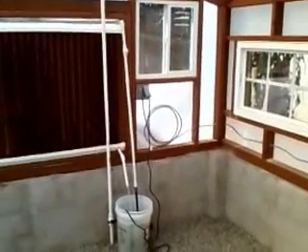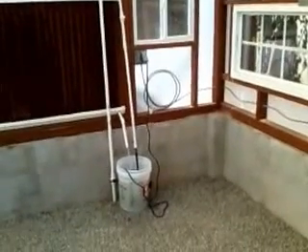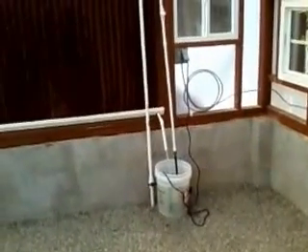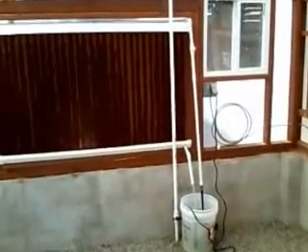Right now, with the weak fan, it's not cooling or ventilating the way it's supposed to. I should feel airflow all the way across. When I do, the plants will like it — they like ventilation. I'll be able to regulate the temperature, keeping it around seventy-five or eighty degrees. These evaporative cooling pads will cool at least twenty to thirty degrees below whatever the outside temperature is.